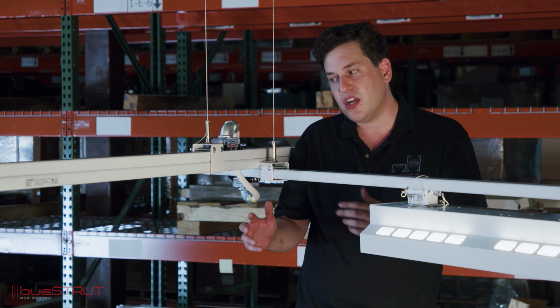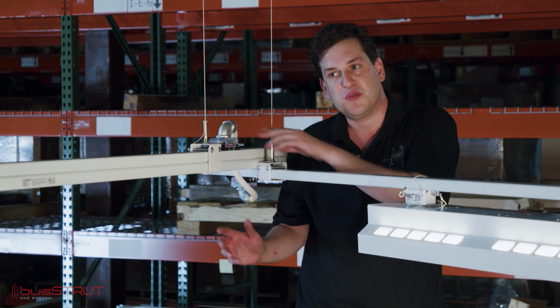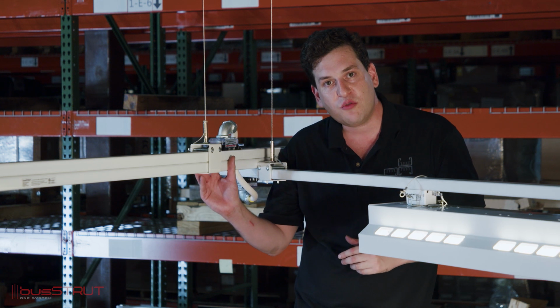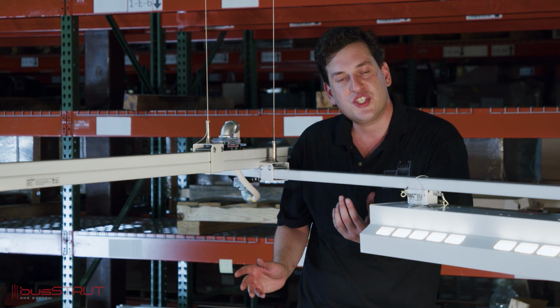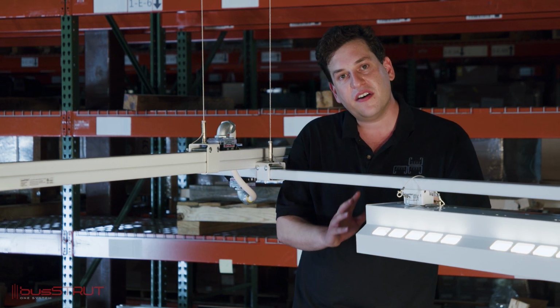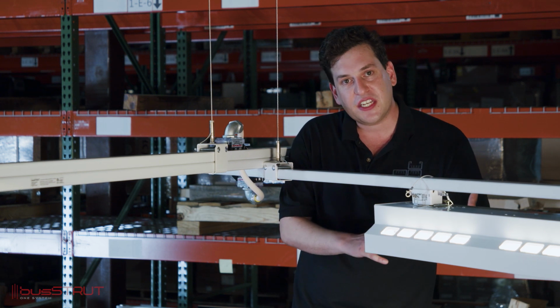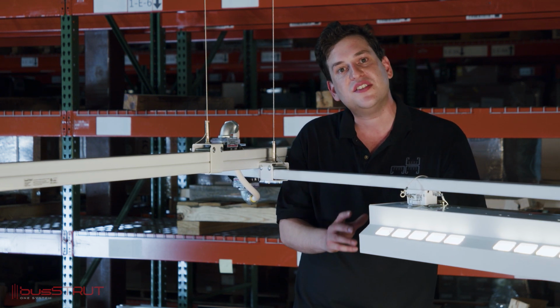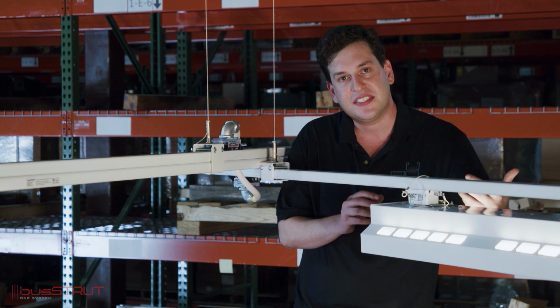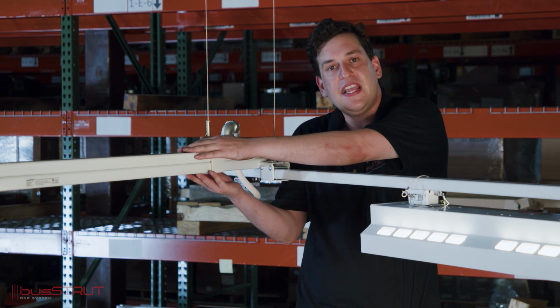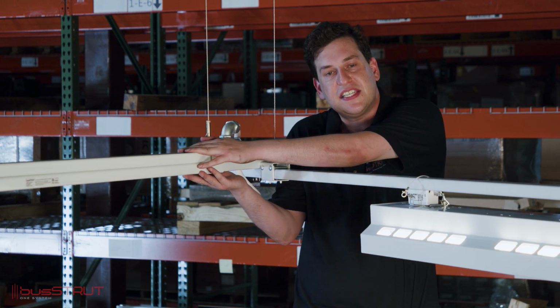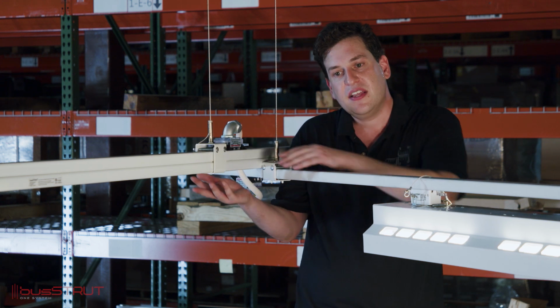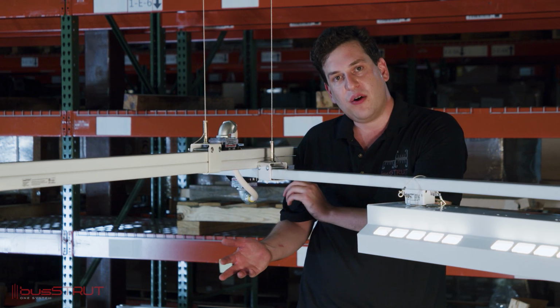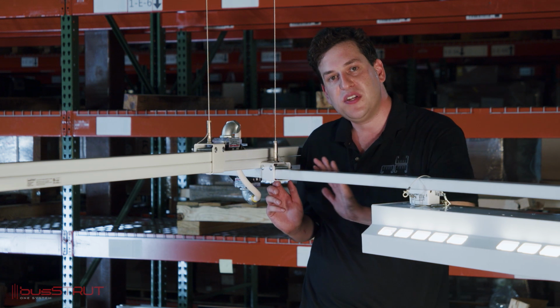Instead, busSTRUT only requires one fuse between the feeding trunk run and the branch of busSTRUT. So all the devices, light fixtures, power drops, you don't need to fuse each device. Instead, this 40 amp, 4 circuit, 160 amp total busway is fused down when the power is distributed to a branch.